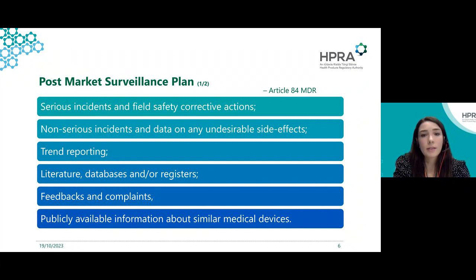The post-market surveillance plan should set out proactive and systemic processes to collect and analyse information concerning serious incidents and field safety corrective actions, non-serious incidents and data on undesirable side effects, information from trend reporting, relevant literature databases and/or registers, information including feedback and complaints provided by users, distributors and importers, and publicly available information about similar medical devices. Adequate systems need to be in place to log all complaints and feedback in relation to a device, and complaints should be reviewed for relevance to safety by categorizing, triaging, and recording any decisions.